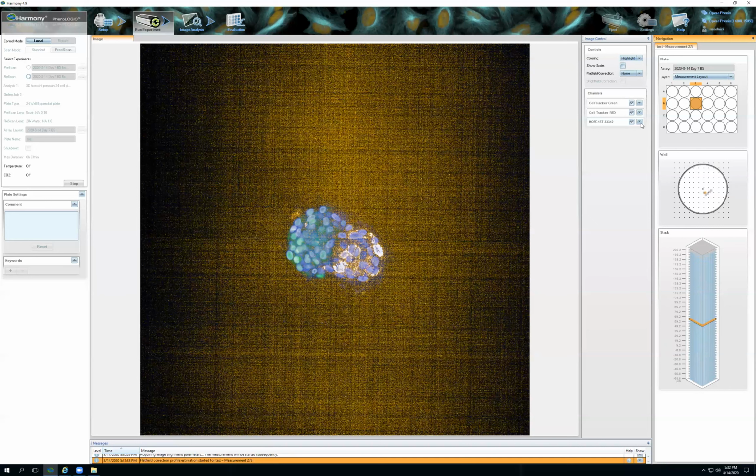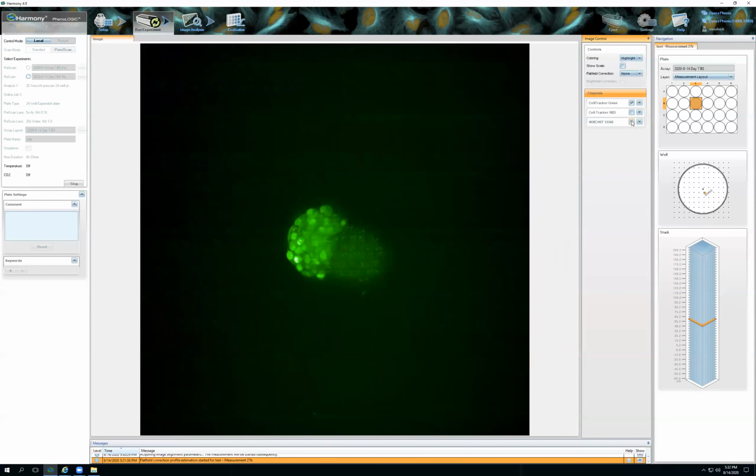So basically you can come over here on the right, and this is going to show you what you're actually looking at. So I'm going to start and go channel by channel. I'm going to right click, I'm going to do show intensity, and I'm going to just go through my channels, click here. Ideally, I want my intensities all the way through to be at least 2,000 or 3,000. So I'm going to say that this one needs to be bumped. This one needs to be increased. So we need to increase the green.